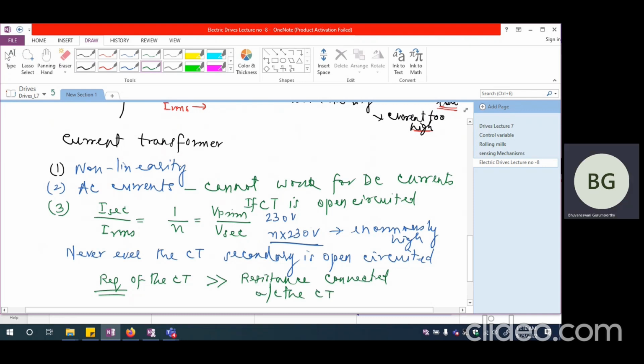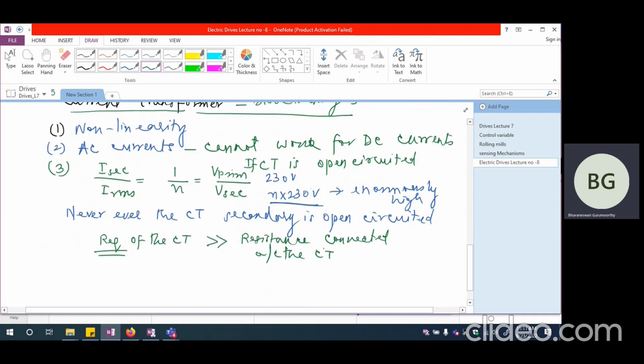So looking at the current transformer, the disadvantages are: one is non-linearity, the second is it can be used only for AC current, and the third is that if by chance I open circuit the secondary, a very high voltage is going to be induced. These are the problems with the current transformer.